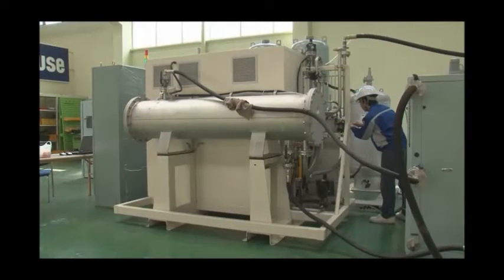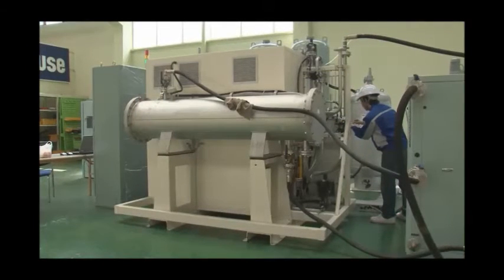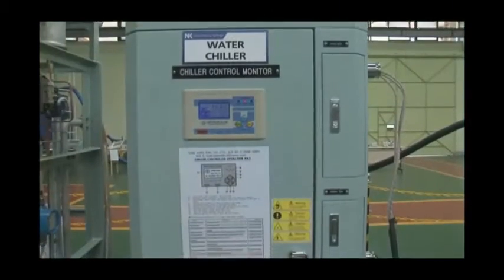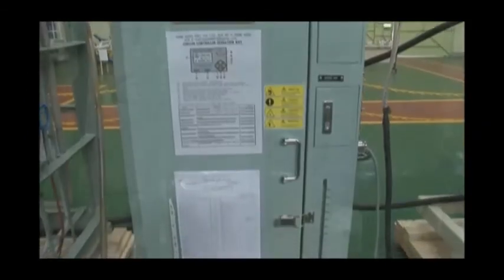During ozone generation in this generating chamber, the high temperature is induced and it shall be cooled down below 40 degrees Celsius by water chiller for proper production of ozone.